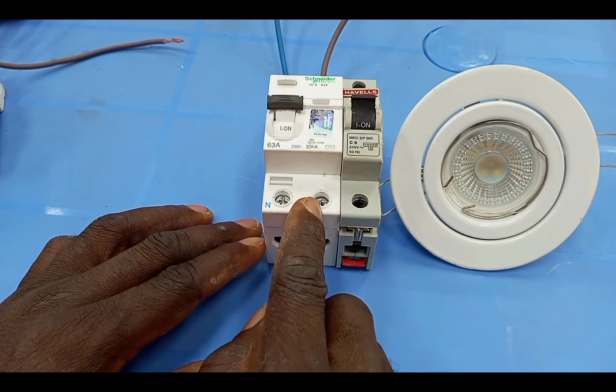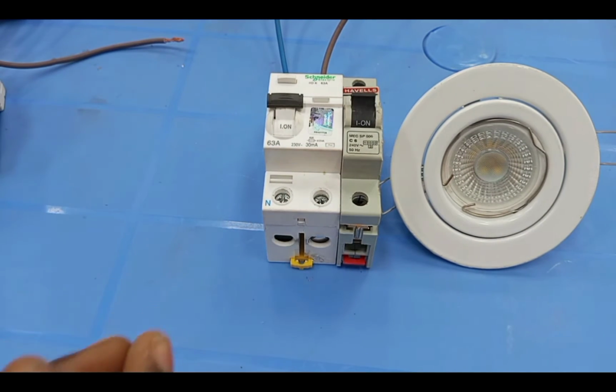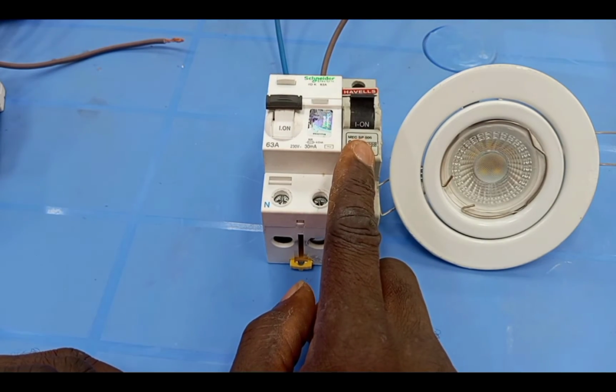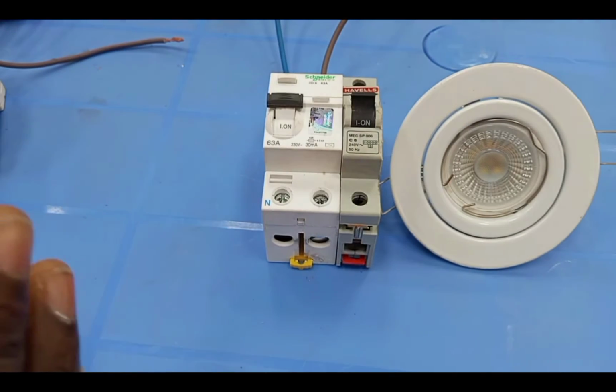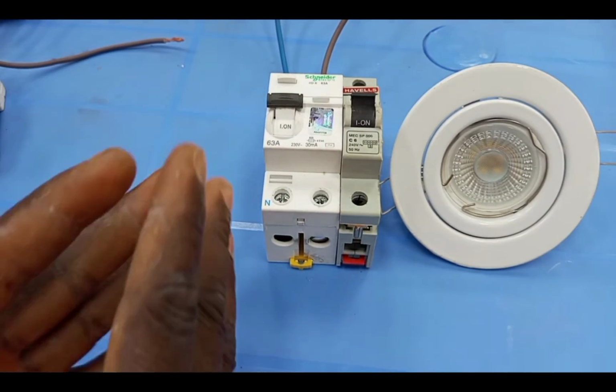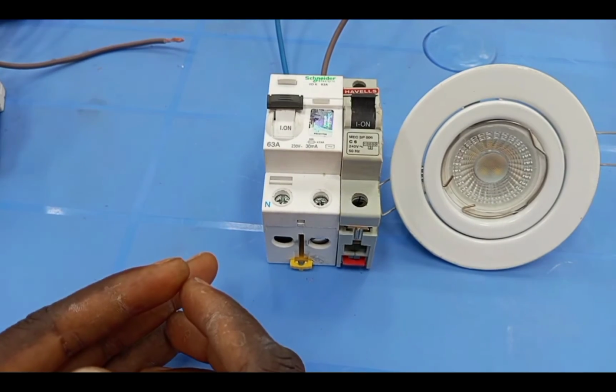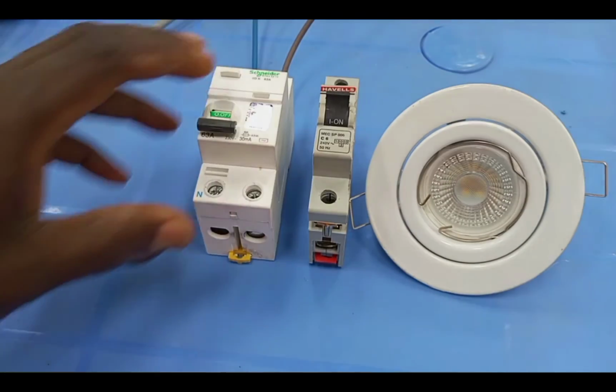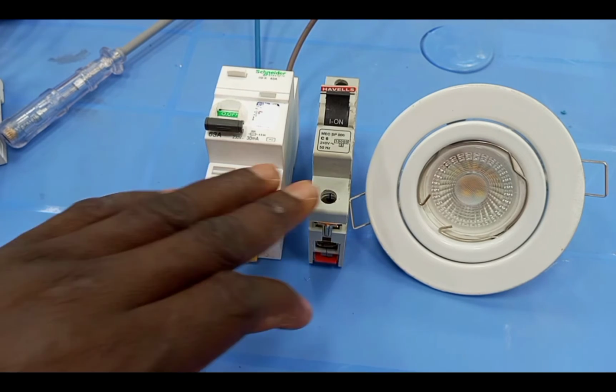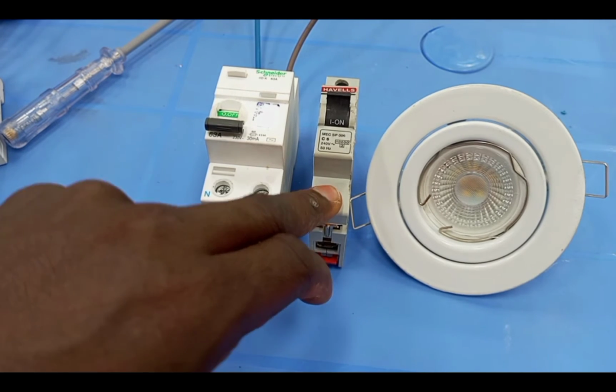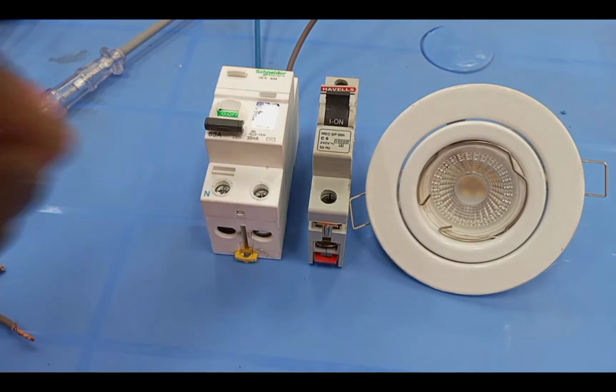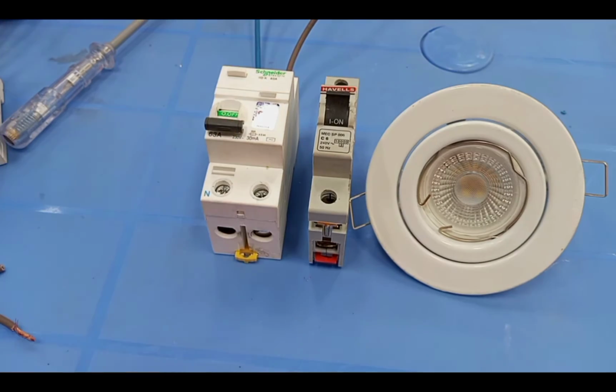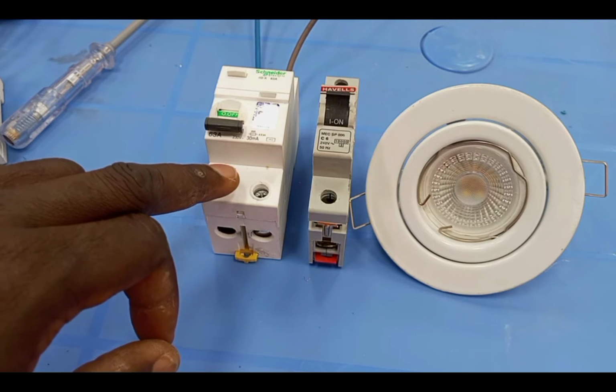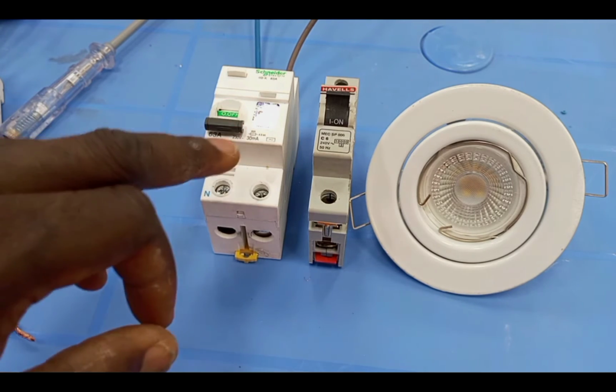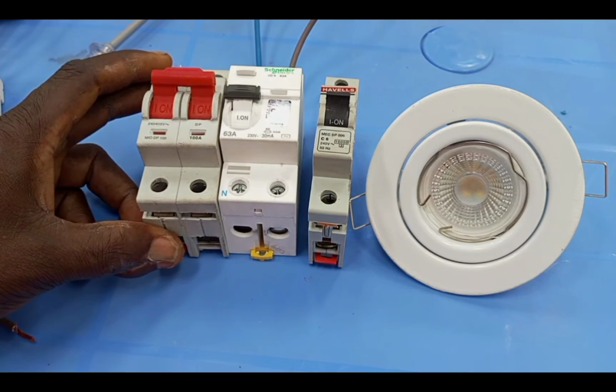As the RCCB is protecting the users, the human beings, from electrocution, the MCB is also protecting the wires and the whole circuit from excess current, which could result from overload or short circuit. All right. So now I have my RCD connected. I have my MCB also connected. But in the case where you want to use this RCD for the whole wiring, then you cannot use the same RCD as the main breaker. There must be a miniature circuit breaker.